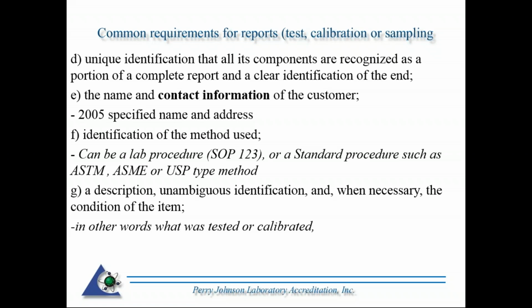G, a description, unambiguous identification, and when necessary, the condition of the item. In other words, if you look at the report, basically what was tested, what was the sample, what was the instrument that was being calibrated? It needs to be identified exactly what it was. Perhaps even make and model would be sufficient in complying with G here.